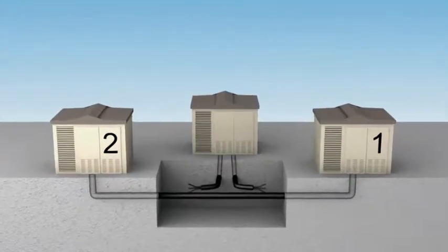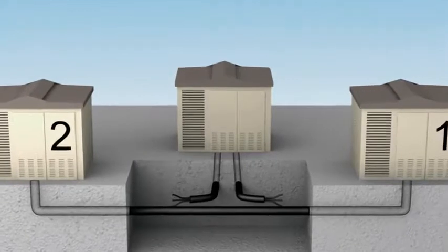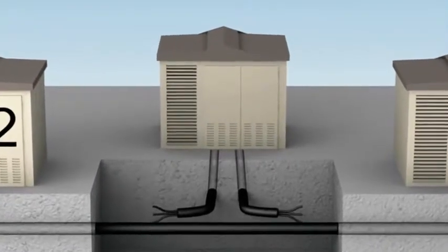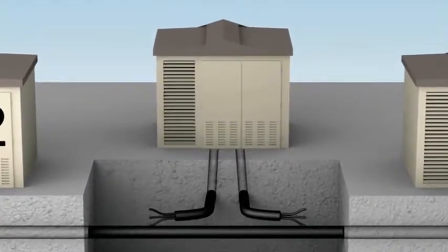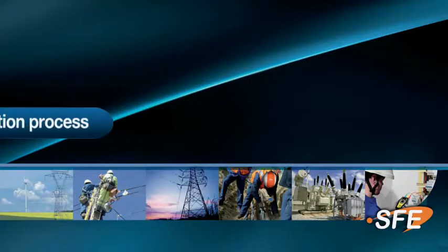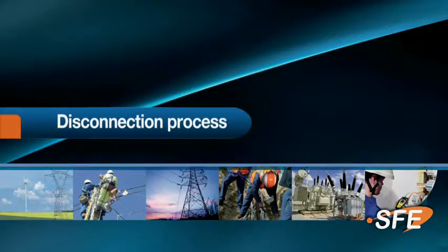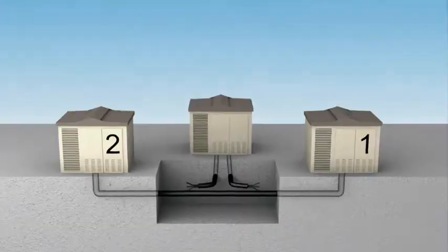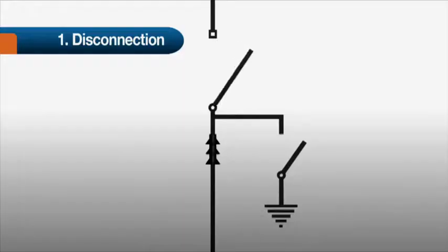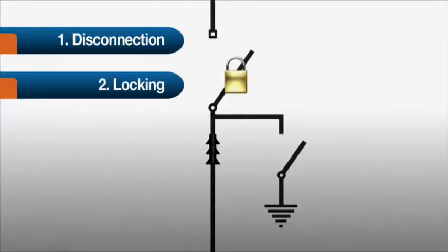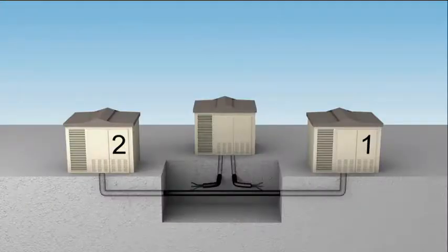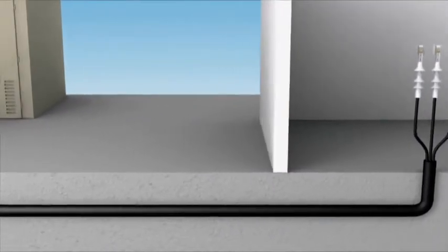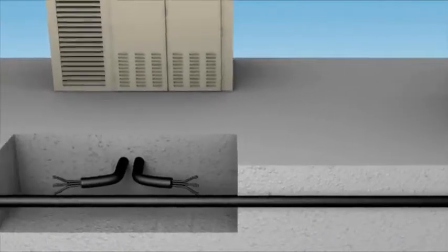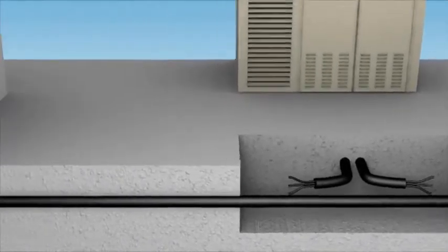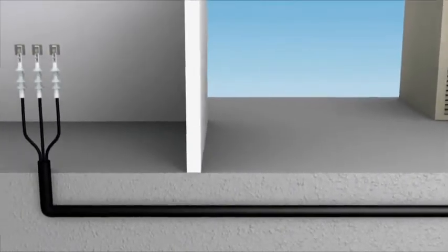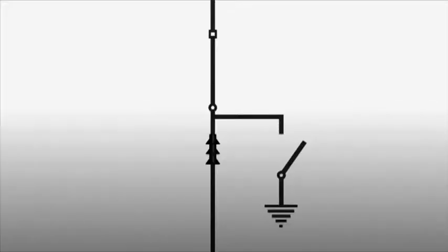Today's intervention consists in preparing the connection of a new substation. Disconnection operations start with the opening and locking of the switch in what we will call here Substation 1. The switch for Substation 1 has been opened and locked by the disconnection operator. The cable has been separated on one end, but the cable is still live.